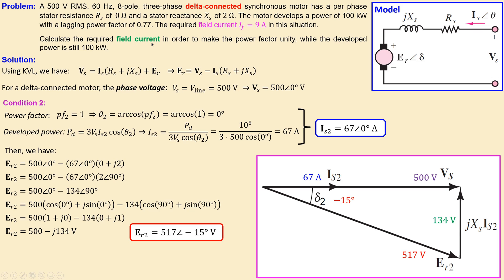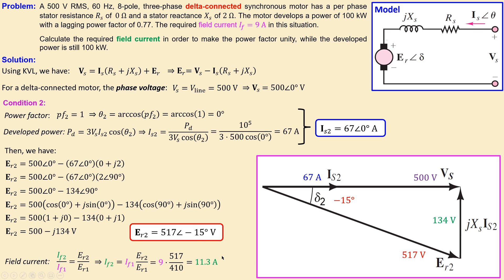To find the required field current for the new condition, we use the proportional relationship: the ratio of new field current to the original field current equals the ratio of the new back EMF to the original back EMF. Rewriting this and substituting the known values — the back EMFs of both conditions and the original field current of 9 amperes — we get a new field current of 11.3 amperes. So the field current increases from 9 amps to 11.3 amps, while the stator current decreases from 87 to 67 amps.